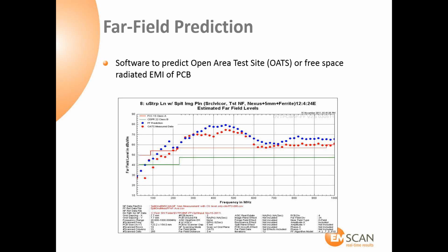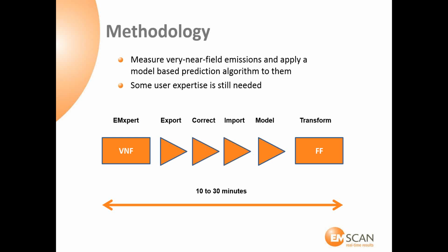Now, essentially the way that this works is you measure in the very near field with EMxpert. We export that near field data, and with this software we do a correction for the near field effects, which is known. We import that into the third-party software, and they do the transformation in the modeling to provide those chamber approximations. So that whole process takes between 10 and 30 minutes to run on your desktop with no other equipment required. So essentially this is giving you certainly one of the cheapest and also one of the fastest pre-compliance tools to give you some confidence on whether or not your device is going to pass or fail when it comes to the compliance testing.